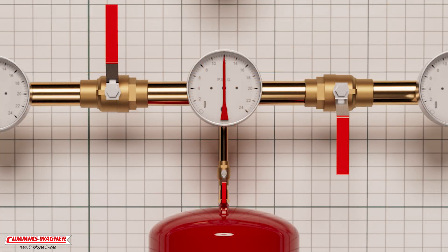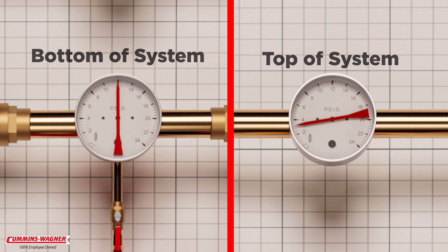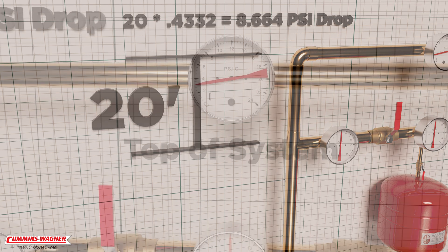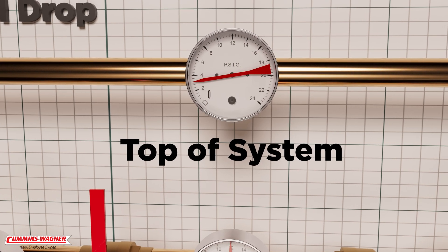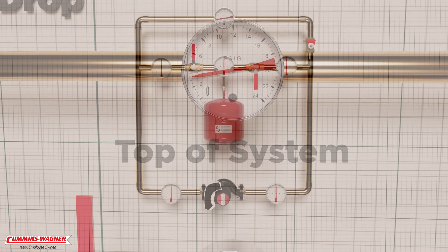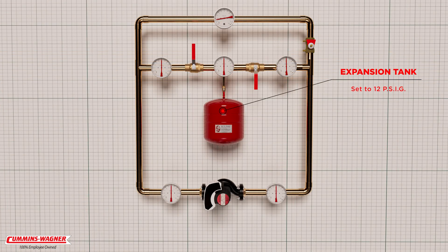The pressure on the system is set to a typical 12 psi. Note that the static pressure at the bottom of the system is not the same as the pressure at the top. In this example, 20 feet represents over 8 psi of pressure drop to get the water to the top of the system, leaving less than 4 psi at the top, even with the circulator off. When we power the circulator, it provides a delta-P, or difference in pressure.